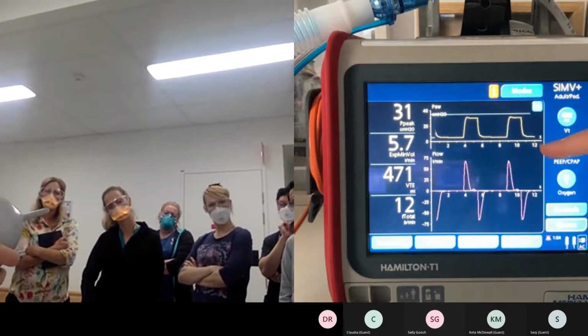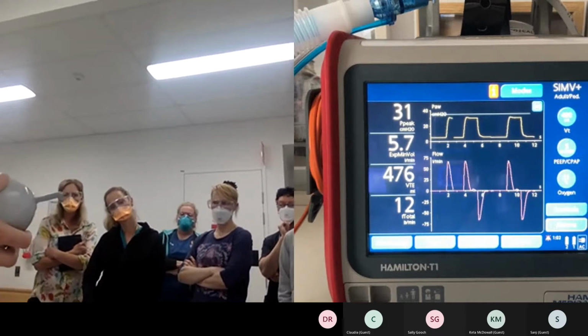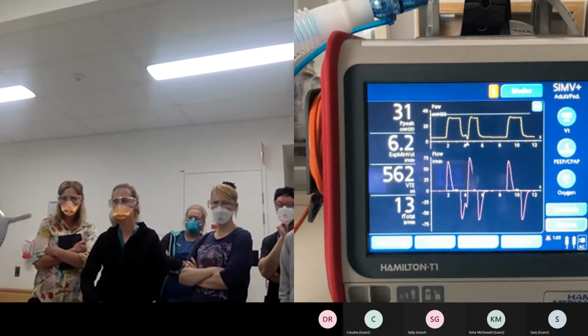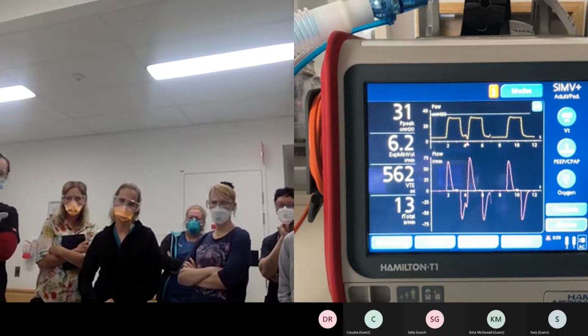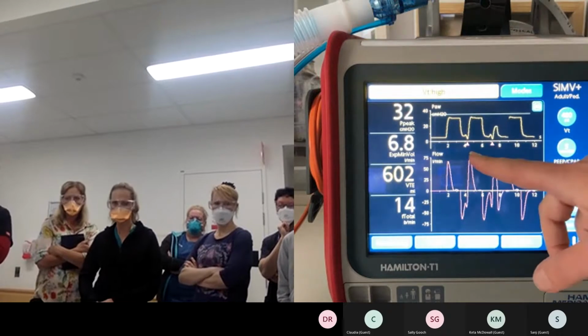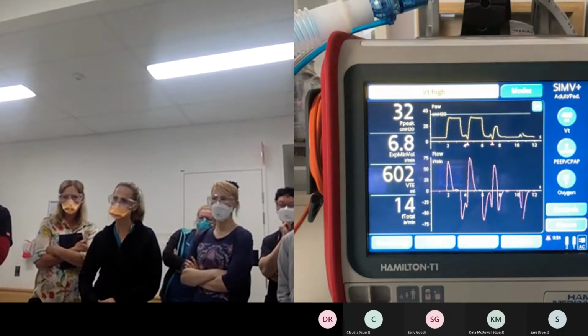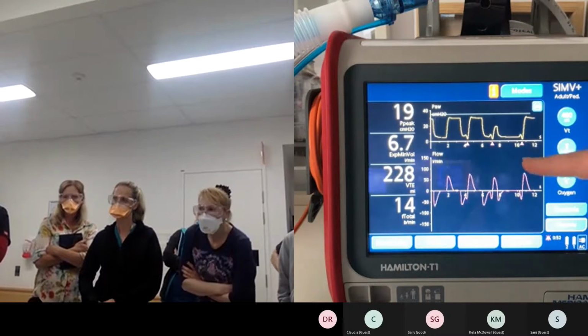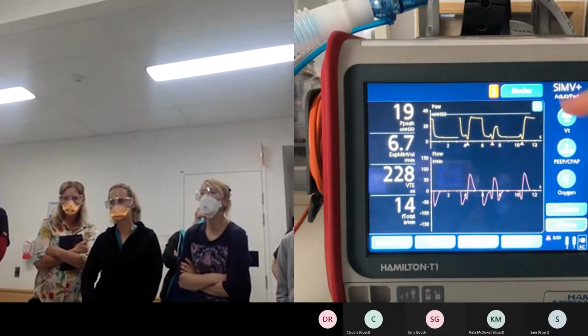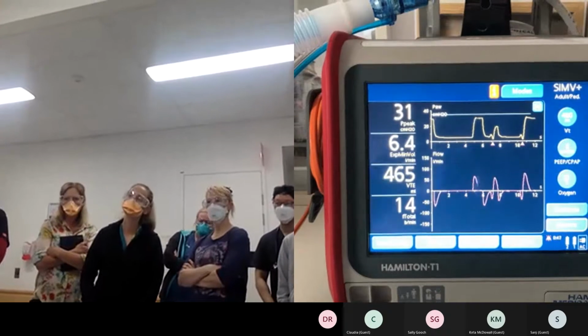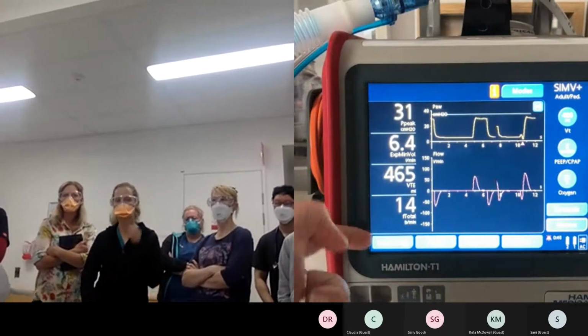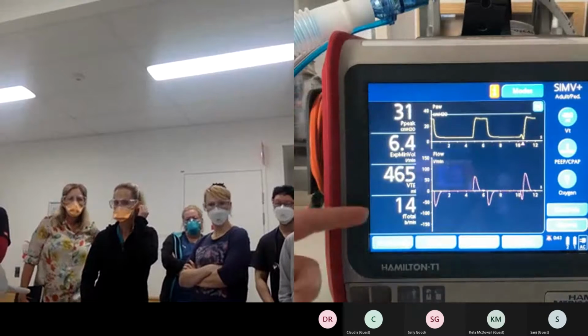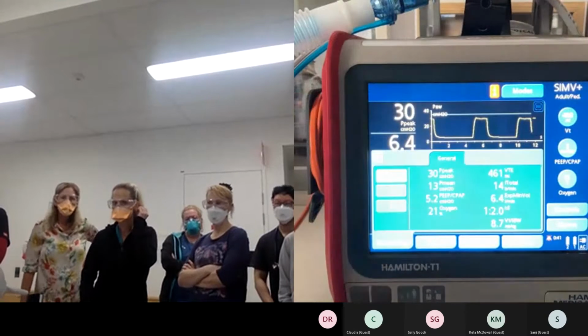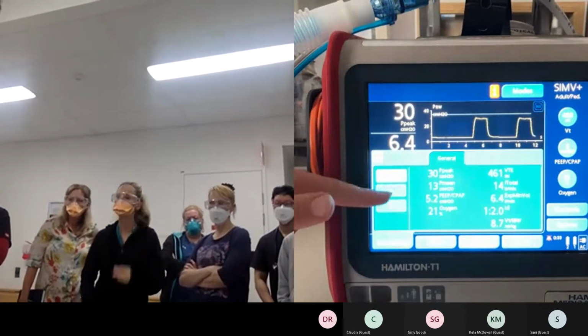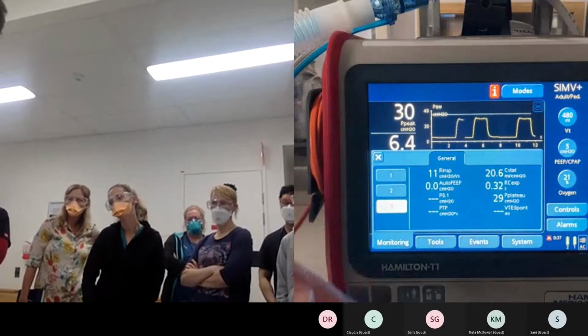Also looking at the pressure waveform, so if your patient starts to breathe, what you'll see happening is little triangles forming underneath when you've got a triggered breath. Okay, so that's what those pink triangles mean. On the left-hand side, you've got your monitored numbers. So we've got 4 on main display. And then when you come into monitoring, you'll find 3 more pages of numbers here for you.